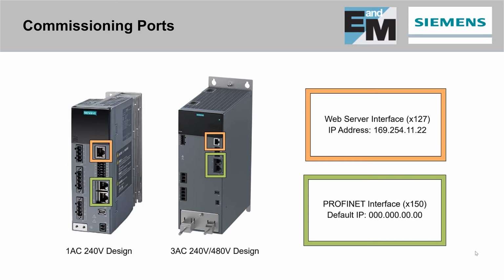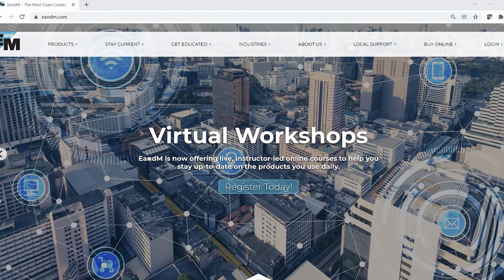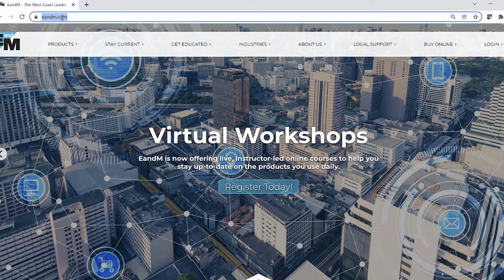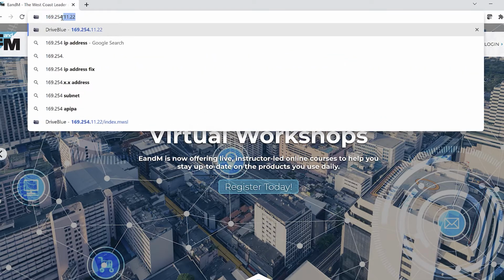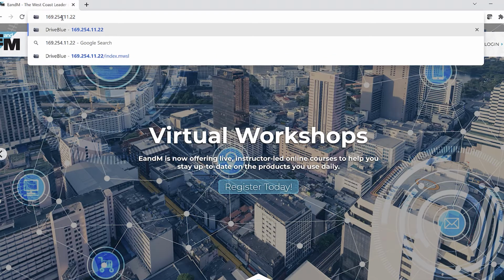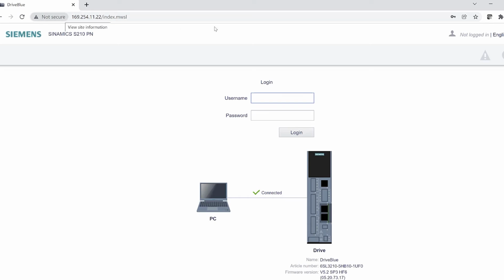in TIA Portal. Once connected to the web server port, on your PC, go to your browser of choice and enter the IP address for the web server. Once the sign-on screen loads, use Administrator for the username, which is the sign-on required for commissioning. Then enter your password. The first time you connect as administrator, you will be prompted to enter the password you would like to use moving forward.